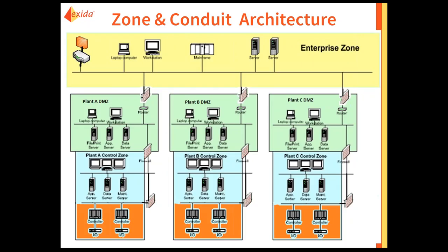Taking that bad example and separating it into zones with conduits: at the enterprise zone we have a firewall and router going out to the Internet. Each plant now has a DMZ — a demilitarized zone — where only enterprise traffic can reach it. We've added another firewall between the DMZ and each control zone, and another firewall in front of the PLCs so only the protocols required to run those devices are allowed through.